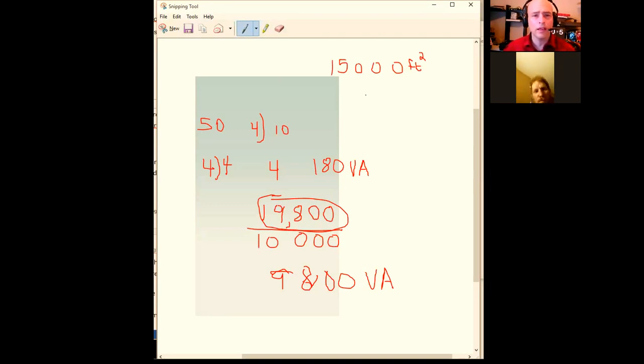Anyway, so 15,000 square feet. I'm looking at 18,360 as the first block answer. What's 120 times 180 come out to be? 21.6. So it's not that much then. What it is going to be is 18,360 divided by 180, which is 102 receptacles. So they give you 102 receptacles in 15,000 square feet. That's what's given in the question. So 102 receptacles times 180 VA is going to equal 18,360. All right, so that's the very first answer to choose from.